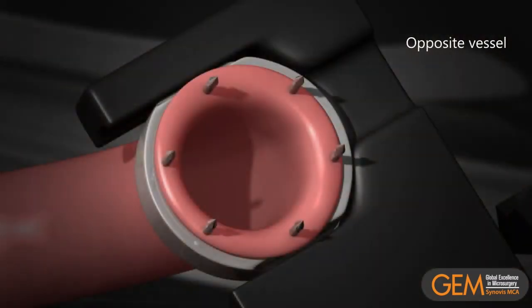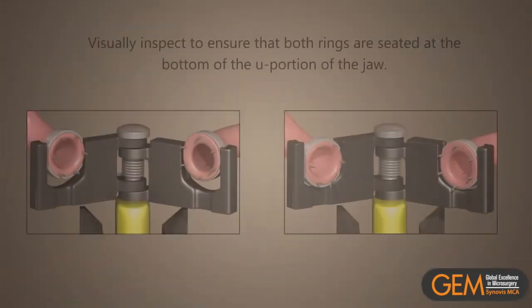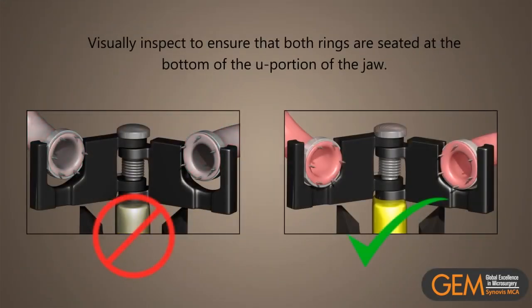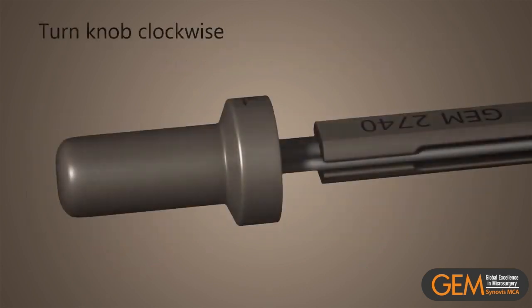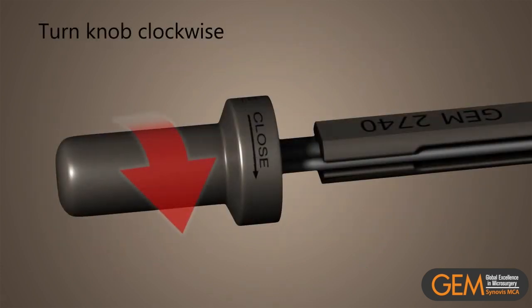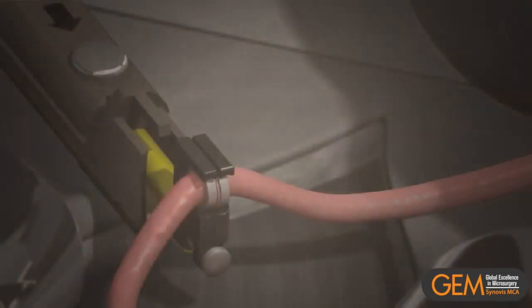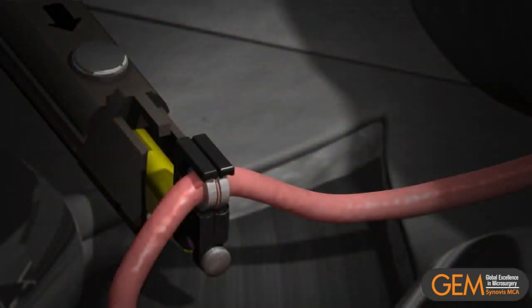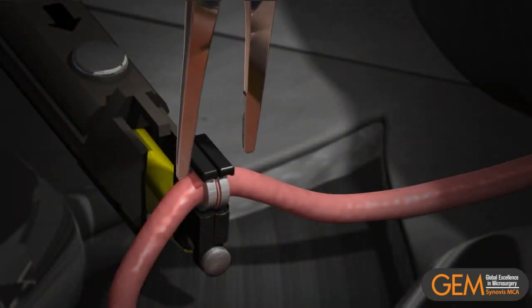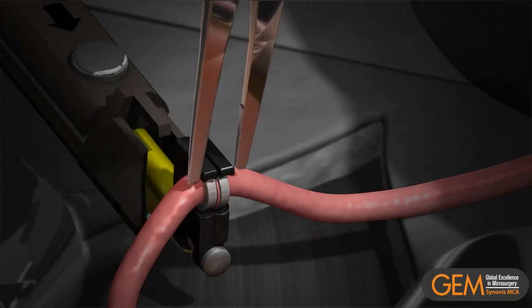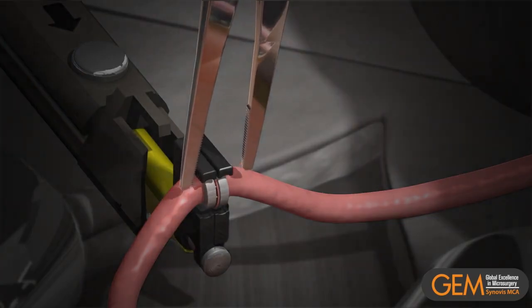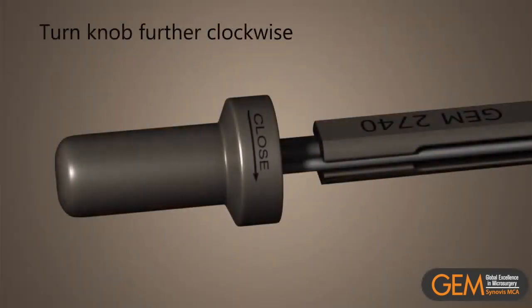Repeat steps to impale the other vessel end on the second coupler ring. When both vessel ends have been suitably impaled, visually inspect to ensure that both rings are seated at the bottom of the U portion of the jaw. Bring the rings together by turning the anastomotic instrument knob clockwise. Before ejecting the joined rings, gently squeeze the end of the opposed jaws with a small hemostat to ensure ring approximation and a tight friction fit. Turn the anastomotic instrument knob further clockwise to eject the joined rings.